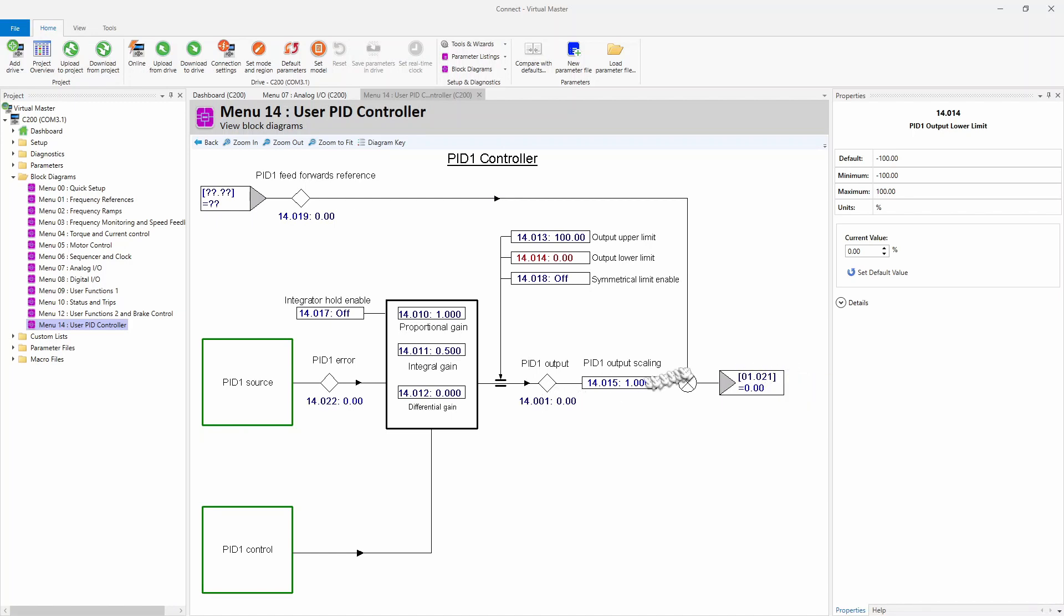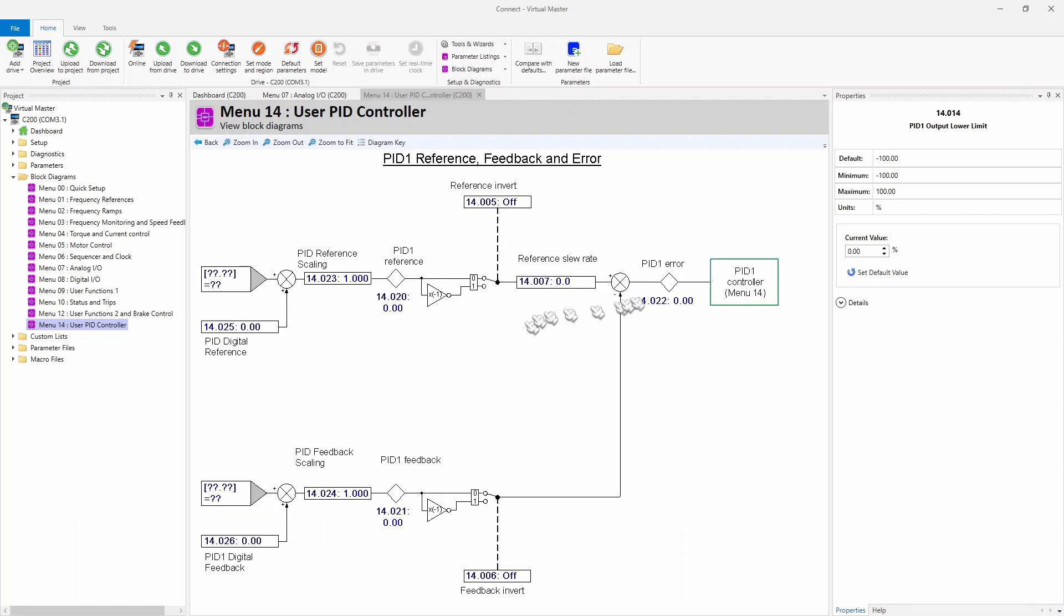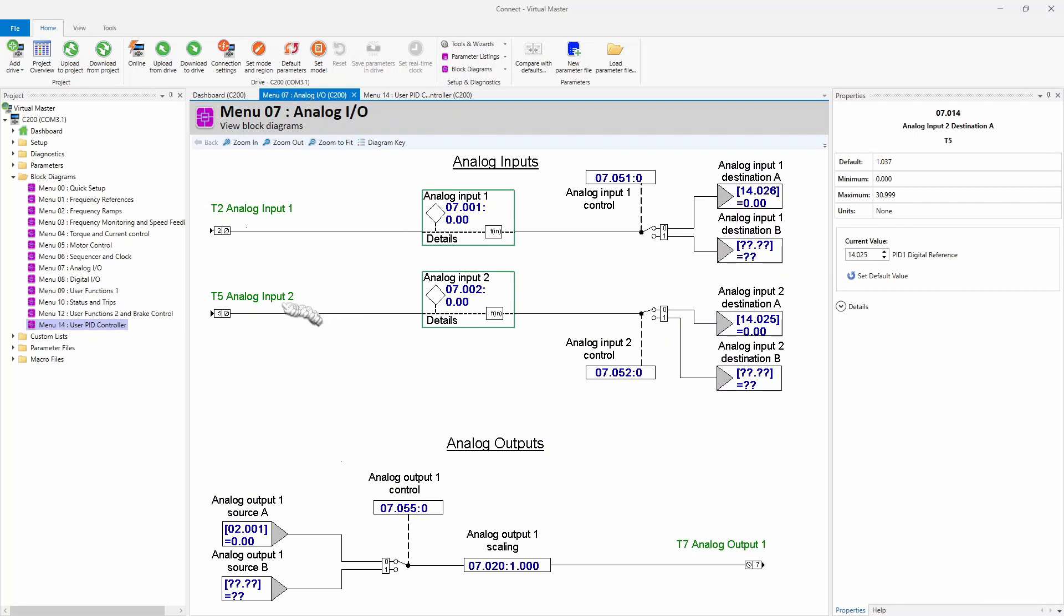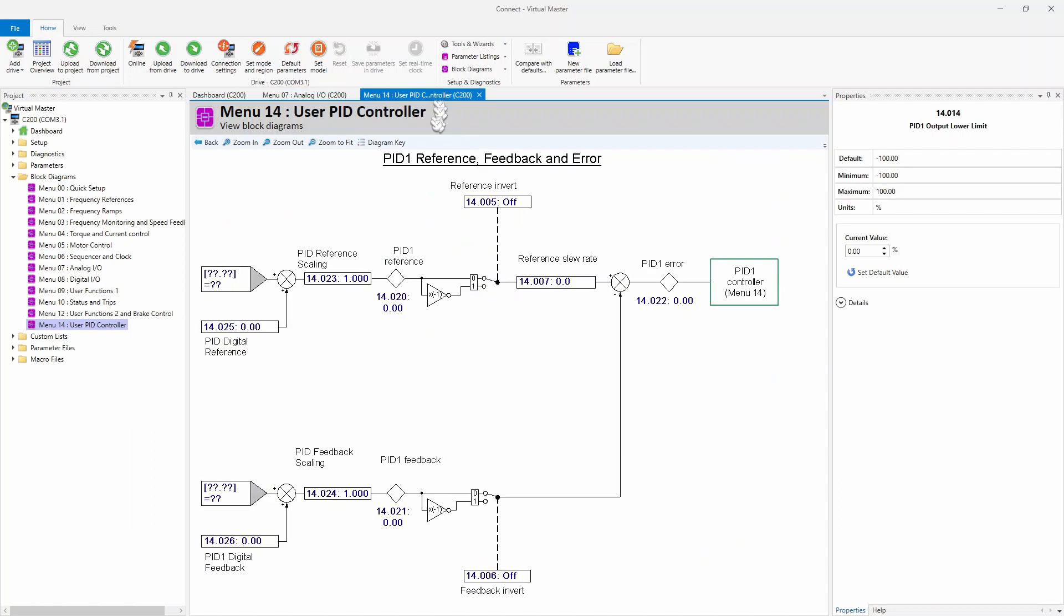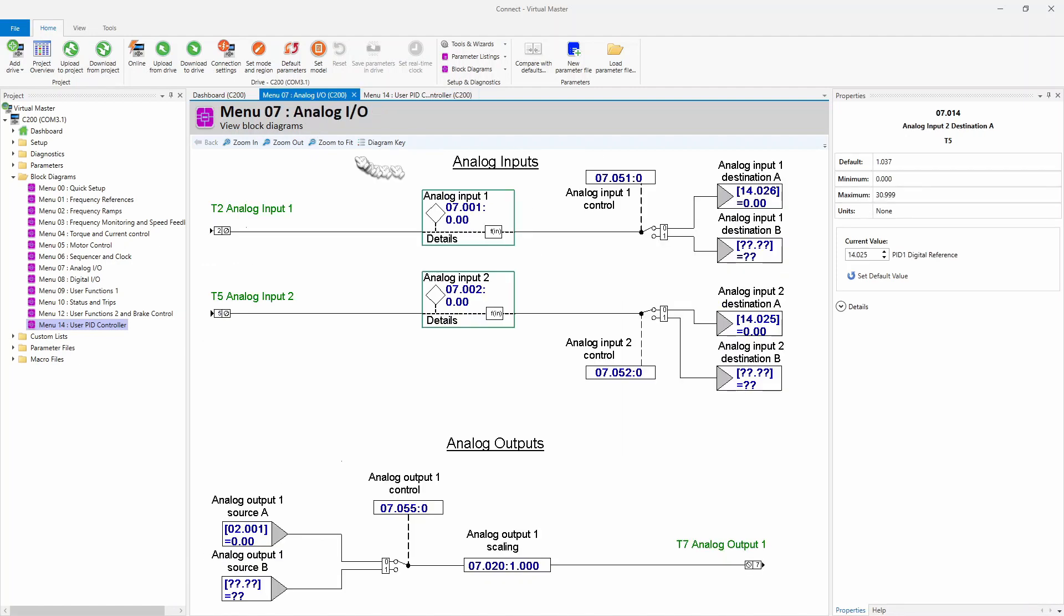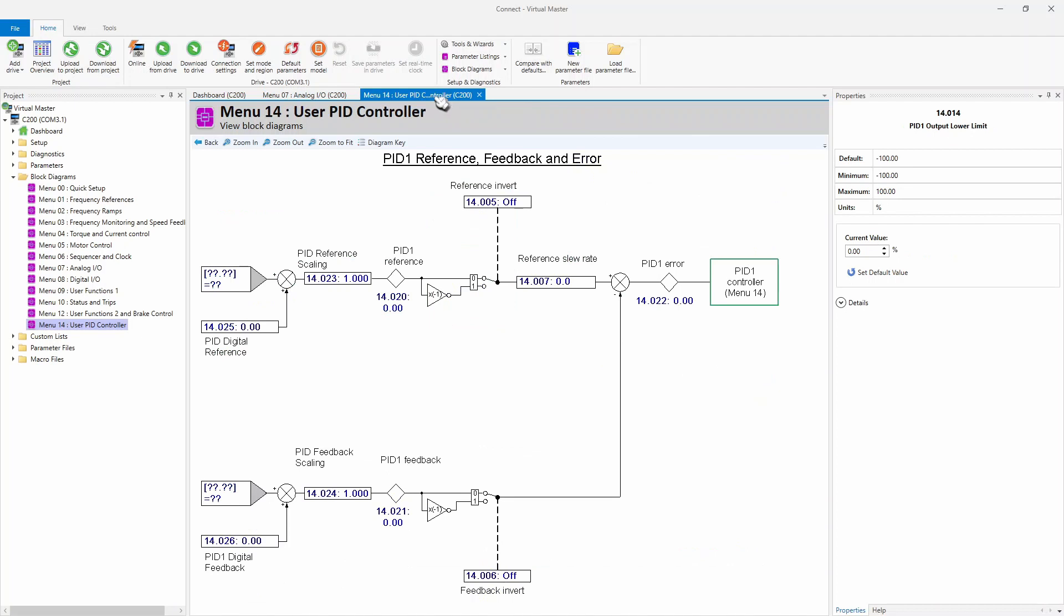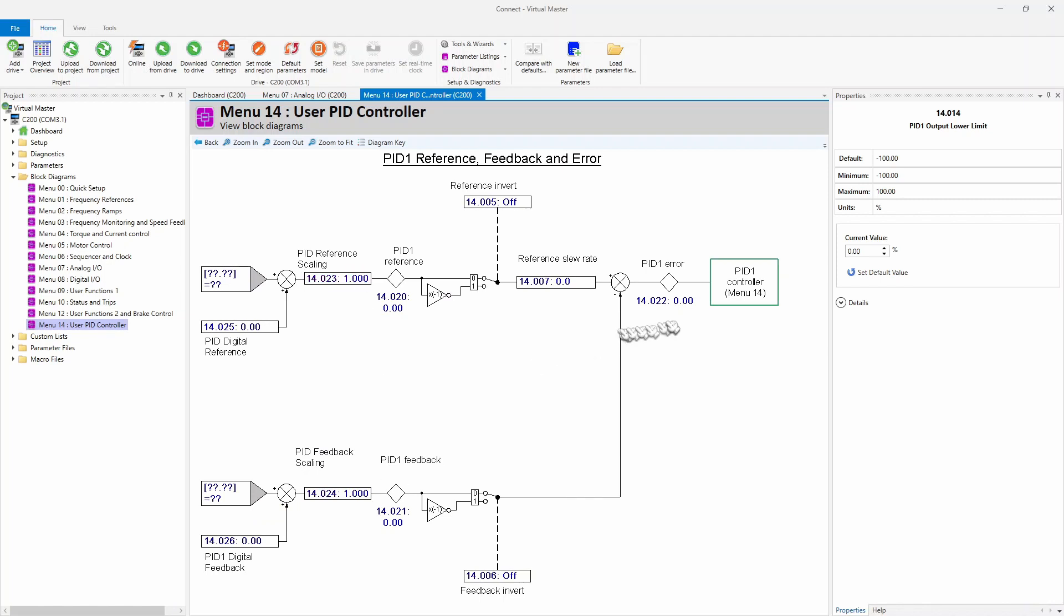The last thing we're going to look at is over here in the source. We're just going to look at this again. So this right here is the PID reference. We set this up. If we go back to our analog, you'll notice that our analog input number two 14.25 is mapped right here. And the data will flow right through until it gets to this subtraction block. And then it shows you the error here. The same thing happens here at 14.26. Now this parameter here, we have analog one tied to it. And so it's getting the pressure feedback through this branch of the input here. And you'll notice that you can actually invert it if your PID acts backwards, or you can even scale it a little bit here. So that's kind of nice. But most of the time, you'll leave this alone.